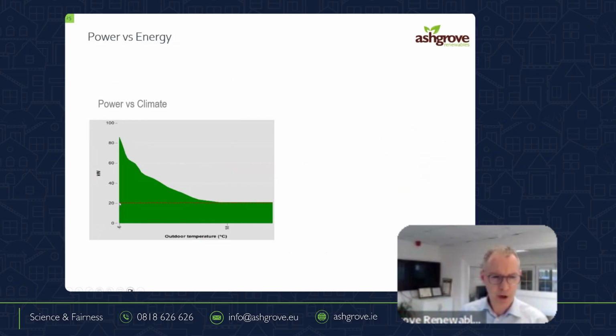In this case, by the way, the apartment block we just looked at, your hot water load is in there as that kind of baseline, and regardless of outside temperature, you're going to need 20 kilowatts worth of hot water, let's just say. So as the weather gets colder, you can see the amount of power that I require for heating starts to climb. But what's interesting is that in Ireland it is very spiky, right? What that means is statistically we get cold weather, but we don't get an awful lot of it. And you'll see that in the next graph.